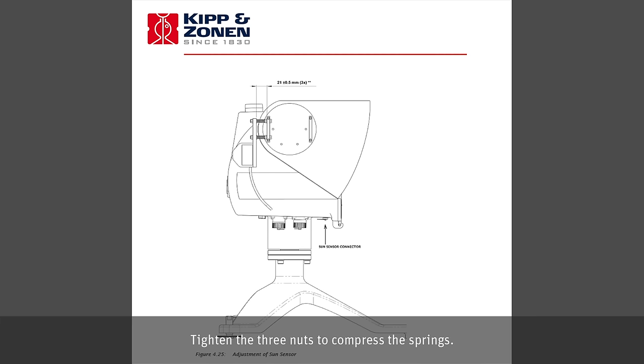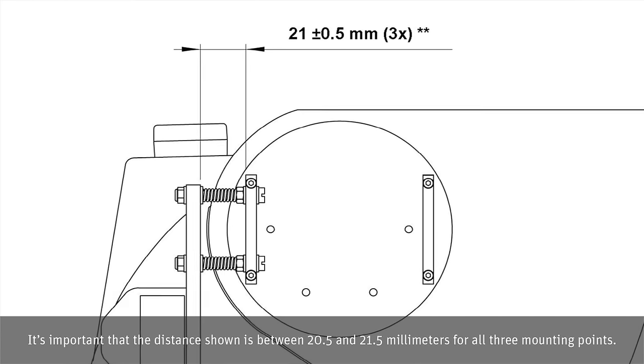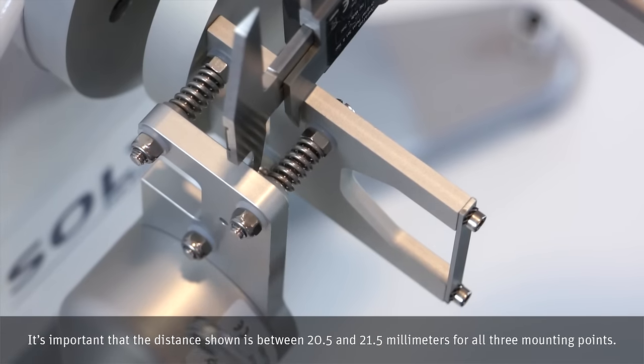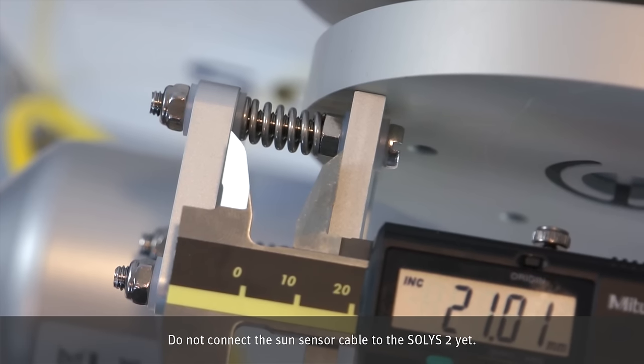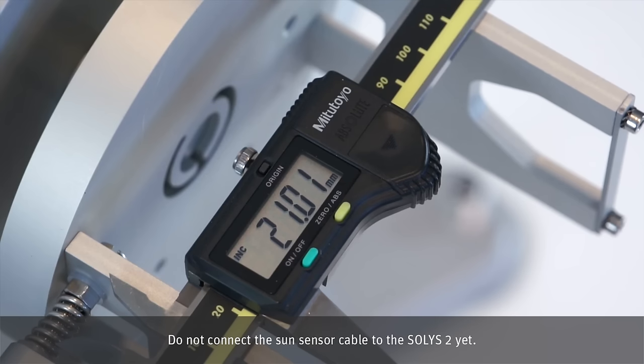Fit the last three shoulder washers into the Sun sensor and hand-tighten the three locking nuts. Tighten the three nuts to compress the springs. It is important that the distance shown is between 20.5 and 21.5 millimeters for all three mounting points. Do not connect the Sun sensor cable to the SOLYS 2 yet.